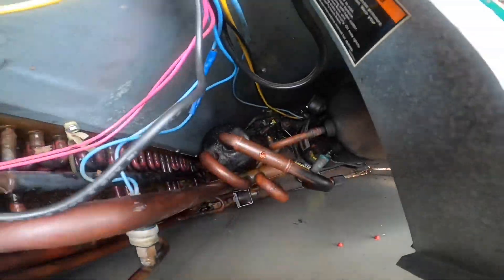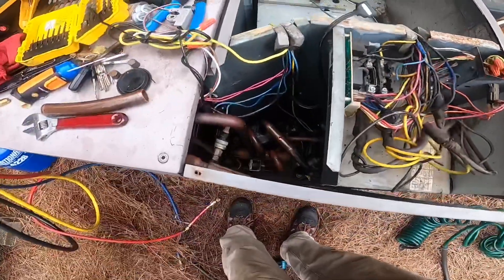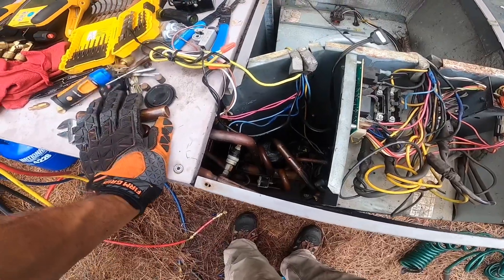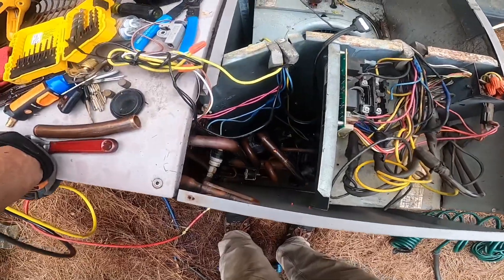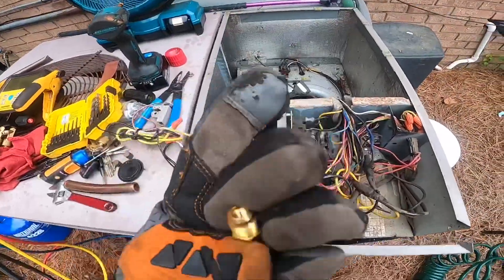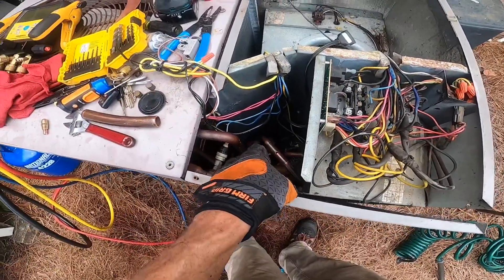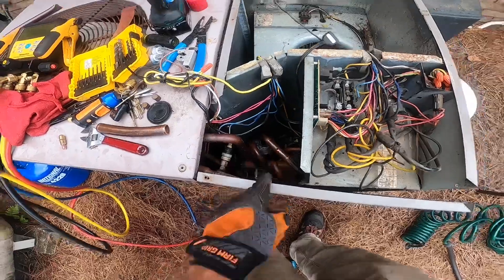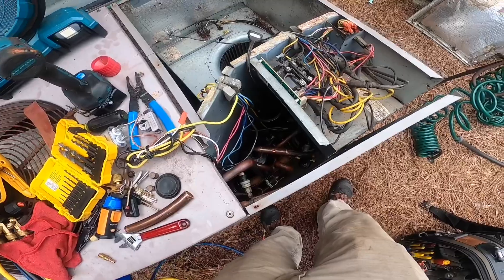All right, so that's what I'm starting with. I've got the seven-eighths piece over the top of it and a hole for my Schrader here. I'm going to leave the hole open and leave the Schrader out when I start to weld, because there's Freon in that accumulator and I need to weld it up with a way for pressure to escape before I put the Schrader in.